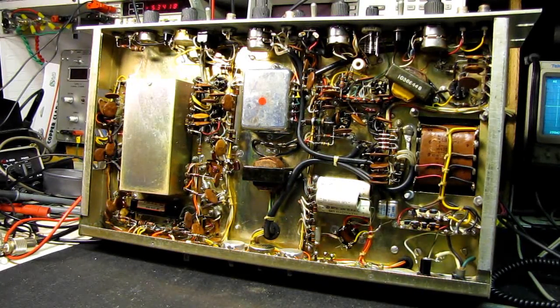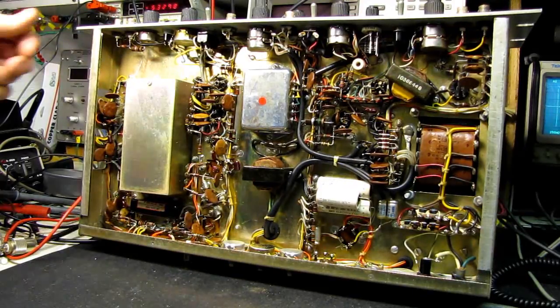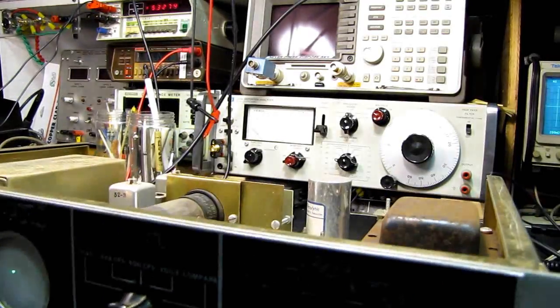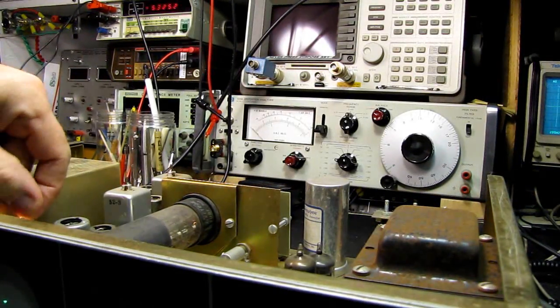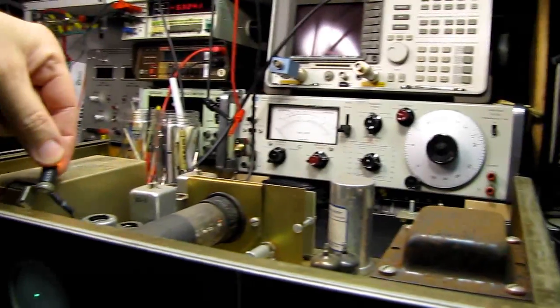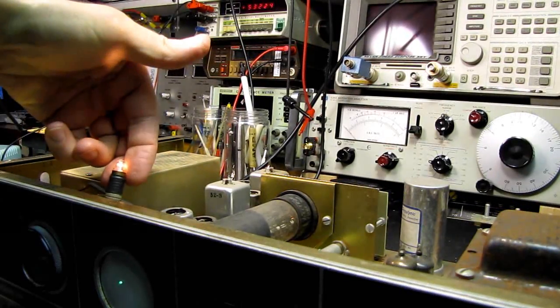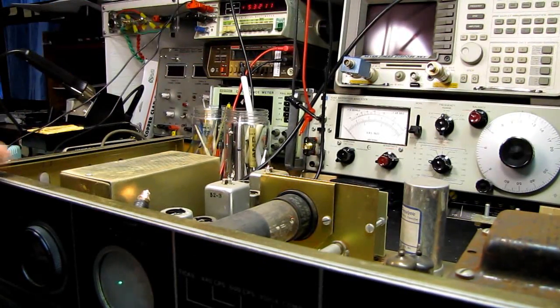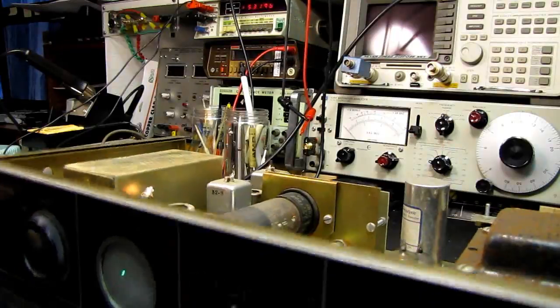I think somebody has modified those. There are 2 lamps in series, one of them just hanging from its socket. So it looks as if somebody put 2 lamps in series to reduce the illumination intensity, or to use whatever lamp they had on hand. I replaced the other lamp, and things are up and working. I don't know if you can see that. That one's lit, as is the front panel right now. The front panel window is lit.